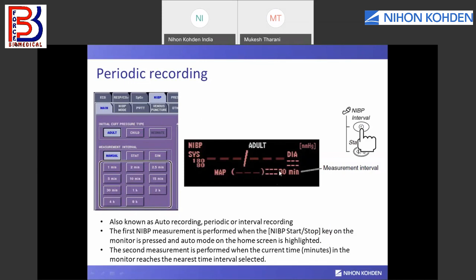Here we are setting two stages. In the first stage we can set STAT, or a 1 minute interval, for 5 or 10 minutes. After the 5 minutes of stage 1 operation time, it will move to stage 2. In stage 2, we can set manual, or 1, 2, 2.5, 5, 10. These options are available for the second stage. So we are setting a two-stage program for NIBP measurement.